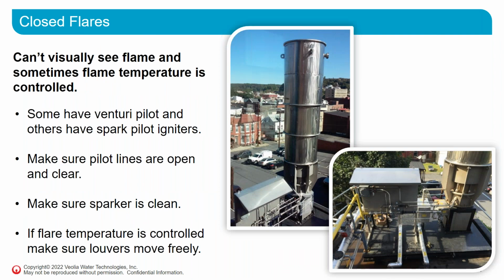With closed flares, you can't visually see the flame, as I mentioned, and sometimes or often the flame temperature is controlled. For the control of the temperature, it has a louver system to control the airflow, which helps control the temperature. So you need to make sure that those louvers move freely so that you have the appropriate airflow, and you need to make sure that the pilot lines are open and clear and the sparker is clean. The general pilot mechanism is similar to that for open flares.